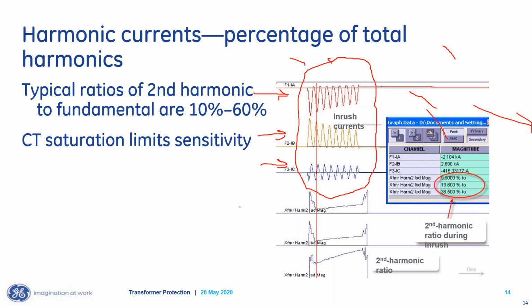And as long as the opening torque was at least 20% of the differential torque that would try to close the coil, the relay stayed open. Right? This worked great for a long time. But what we see a lot of times now is with a modern transformer, we might see a completely different restraint scenario.